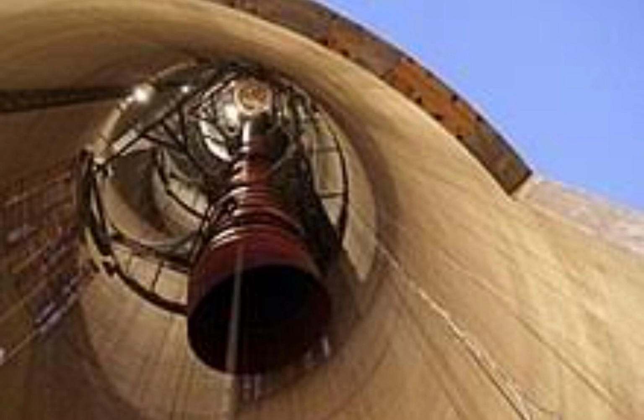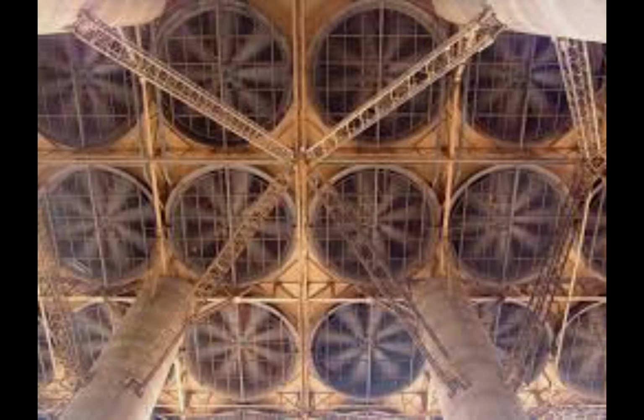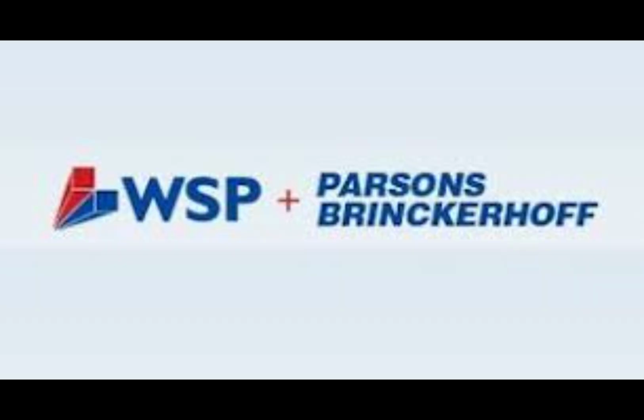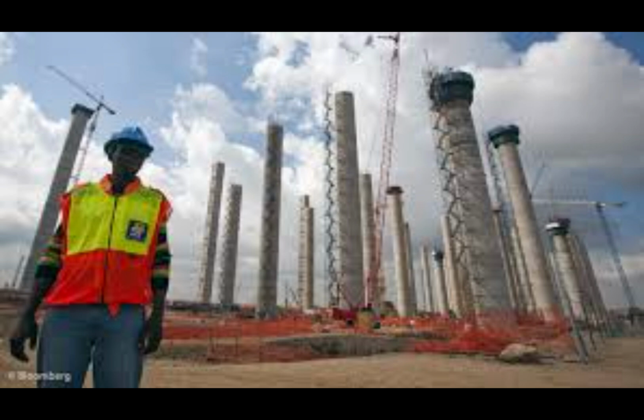The design was changed at a late stage in 2007 and doubled in size to 4,584 megawatts. The boilers were envisaged to be supercritical in type, which would make them 38% more effective than other Eskom power stations. A dry-cooled system was also intended to use less water than other coal-fired power stations in the fleet. Initial project costing was estimated at 69 billion rand, but that was updated to approximately 80 billion rand by 2007. Parsons Brinckerhoff was appointed as the project engineer to oversee all construction.